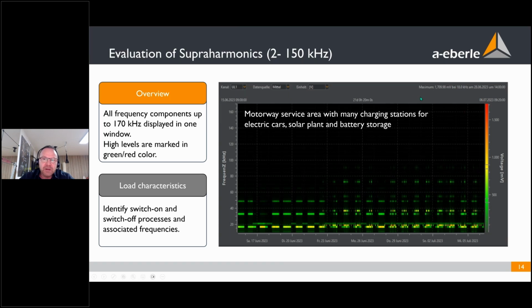The maximum disturbance we find here is about 1.7 volt at 18 kilohertz. Okay, we see here 18 kilohertz is a disturbance we find every day, every working day, every weekend, but not during the night. So this is typical. This is the interference of the solar plant. And if the solar plant here is working every day and brings an interference of 18 kilohertz to our network, then you also see twice 18 kilohertz and three times 18 kilohertz. So these are the multiples of the sampling frequency which the solar inverter brings to our network.